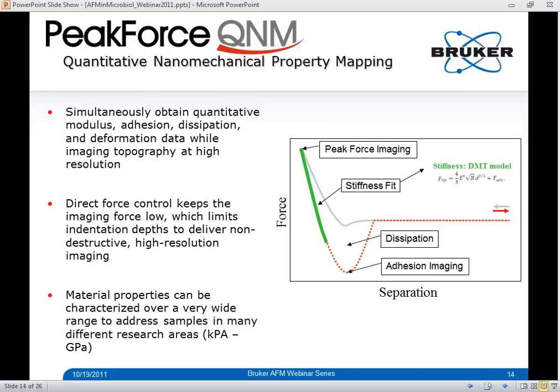Peak Force Tapping also enables Peak Force QNM, or quantitative nanomechanical property mapping. Because force curves are collected at every pixel of the Peak Force Tapping image, these curves can be used to obtain quantitative nanomechanical property measurements as a function of spatial location over the sample surface. In addition to topographical data, Peak Force QNM simultaneously provides separate quantitative two-dimensional maps of modulus, adhesion, dissipation, and deformation that directly correlate to the topography data channel, acquired at typical pixel resolution and imaging scan rates. Material properties can be characterized over a wide range of samples to address many research areas.